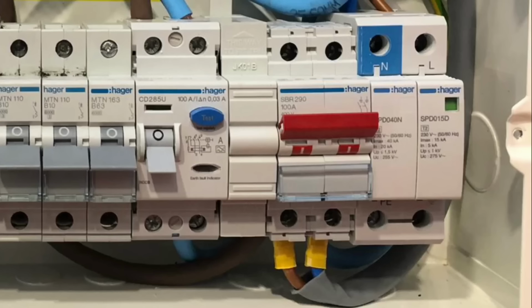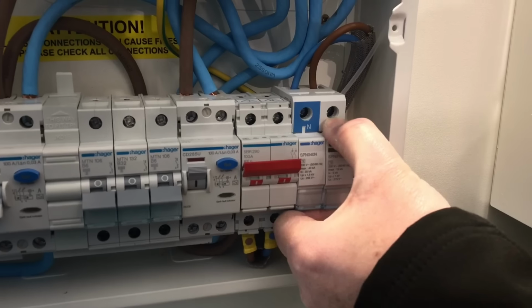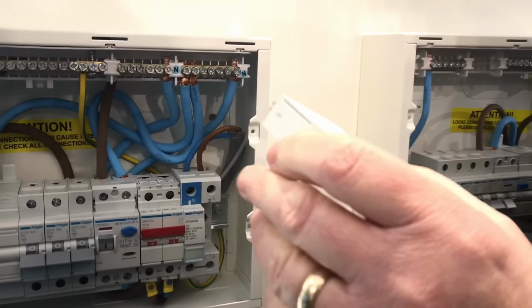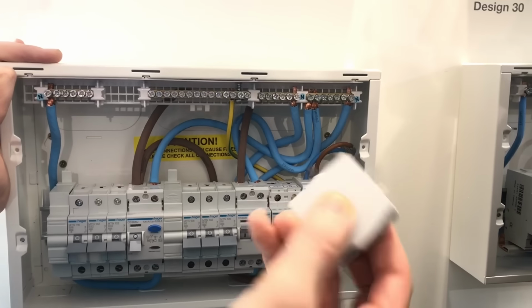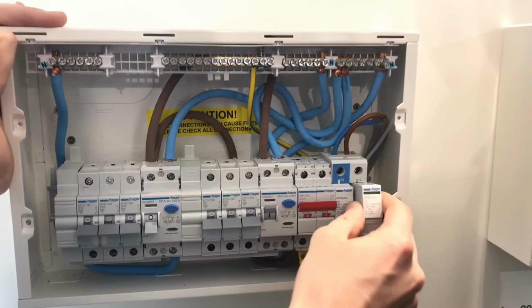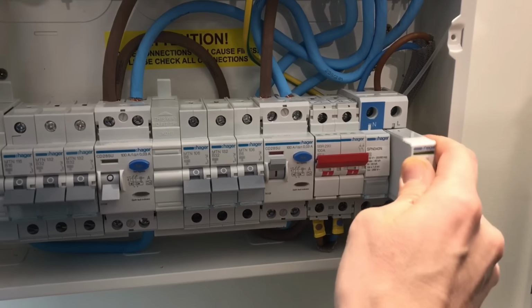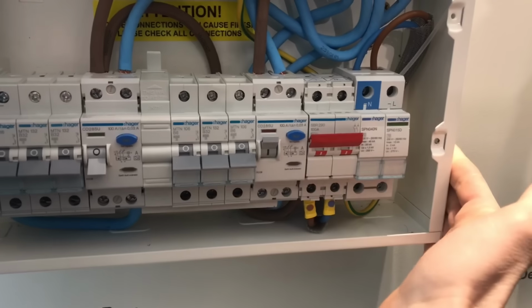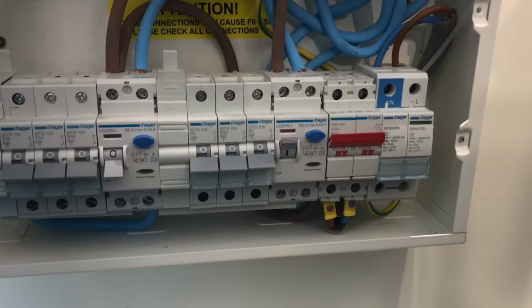Absolutely fantastic. Surge protection, you notice it's got this green window, so as it sees surges, this part of the surge protection device will eventually wear down, and at some point in the future that window could be red. Should that window be red, simply what the customer has to do is pull this cartridge out. Oh wow. Get a new cartridge and simply put it back. That's fantastic. And it's that simple, just a matter of remove that and it just goes back in again. Now I've not done this before on a Hager board, so let's see. And that's it. That's simple as that. Well, that's absolutely brilliant.